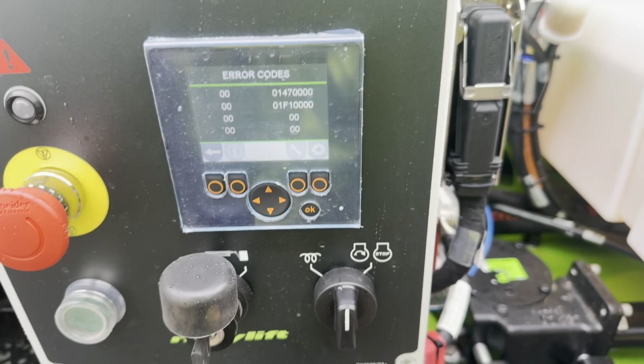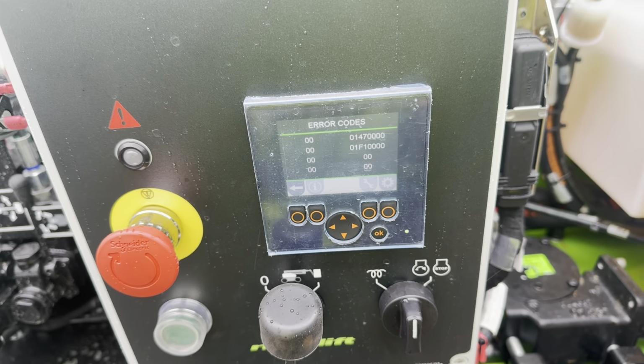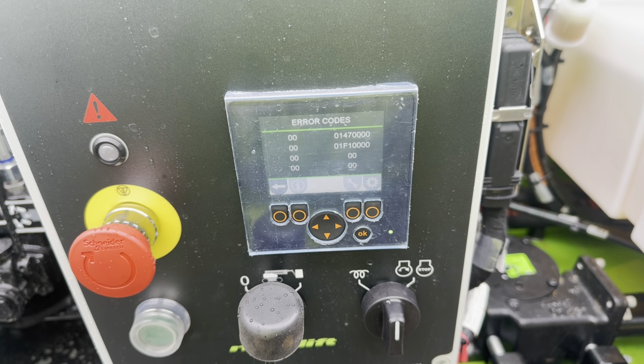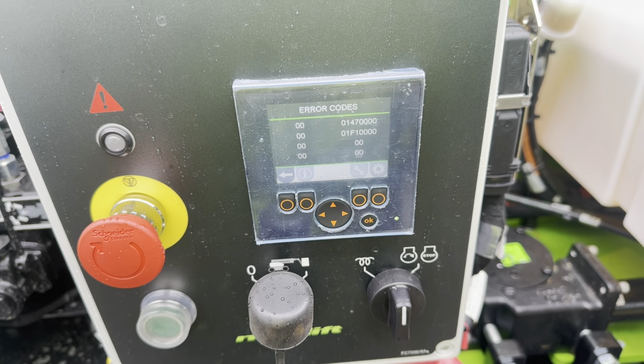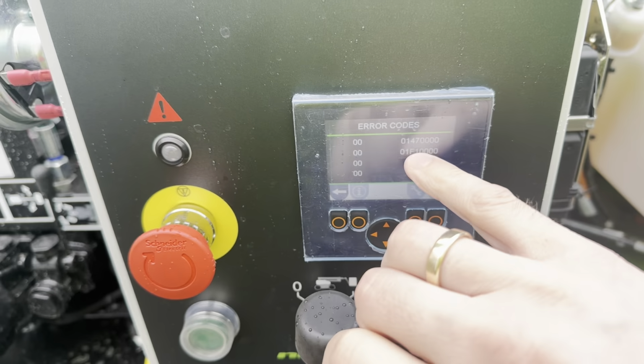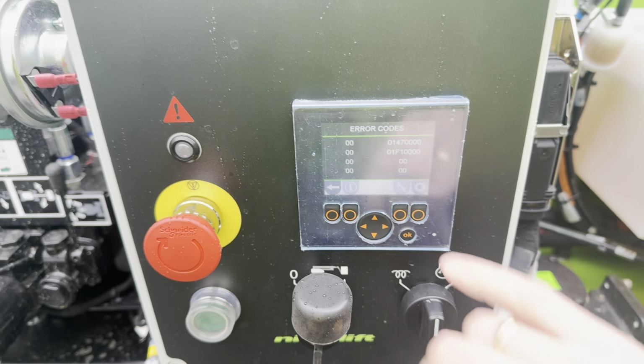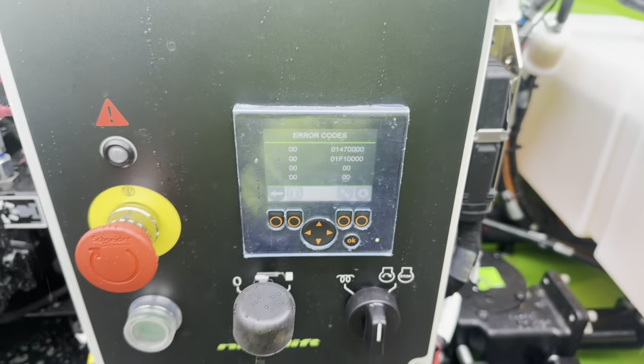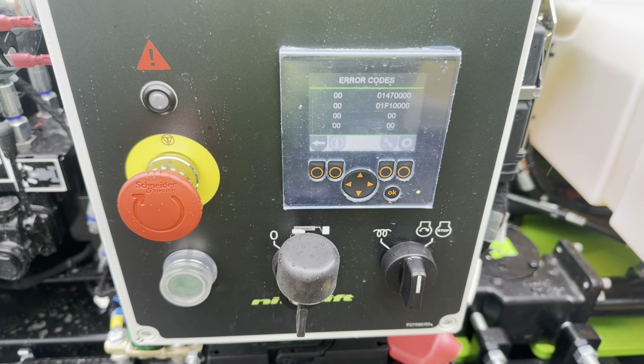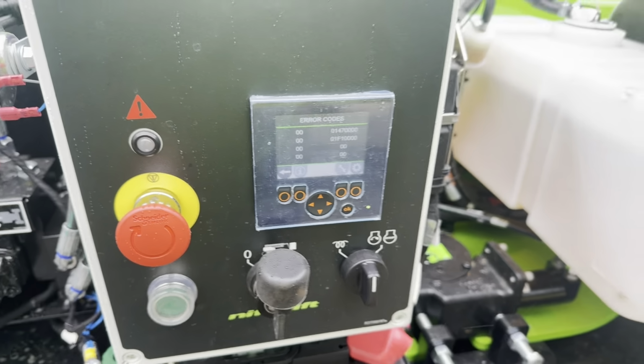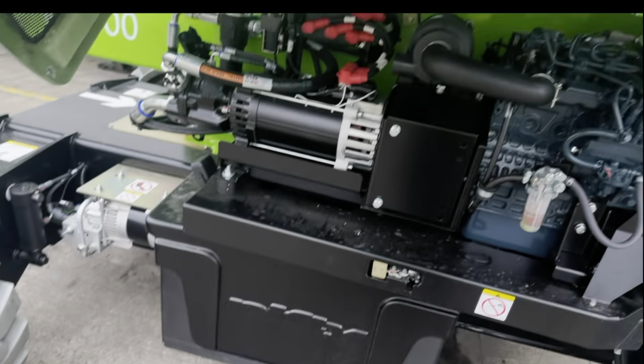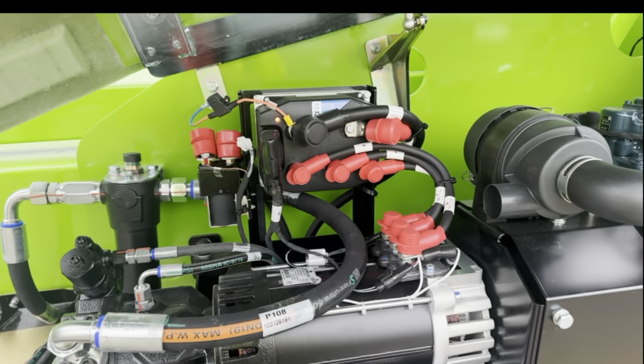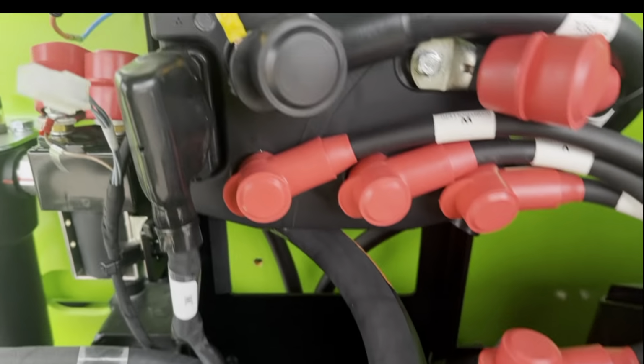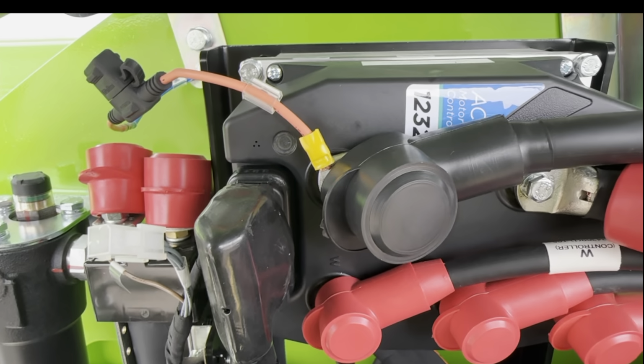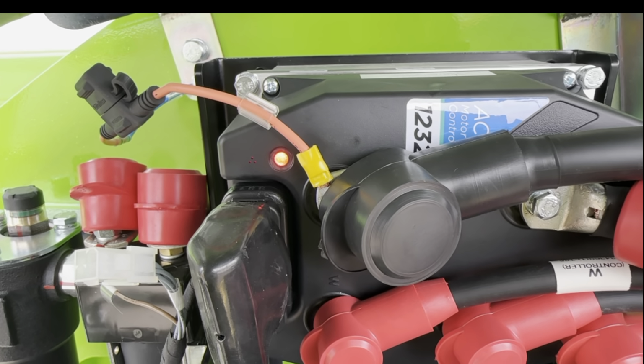So there are the error codes 01, F1 and 147. Without checking, I know this is going to be the motor controller error, and 147 is this motor controller specific error. So we can have a look at the flash code on the controller. That should be flashing something. Engine canopy. So here we have a controller, and it does flash the error code. So let's try to read it out.